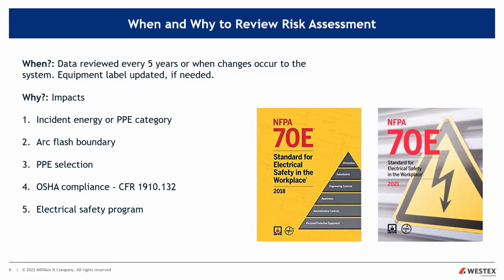Now, why? Well, of course, if things have changed, the incident energies change. Maybe the available fault current has gone up, or maybe you've changed the setting on a circuit breaker where it's a longer clearing time, and that can affect the incident energy. It could also affect if the PPE category is still valid. If you've changed the system a little bit, will it meet those parameters? Of course, if it's higher incident energy, maybe the arc flash boundary is longer than previous, or maybe shorter if you have new equipment. It may reduce your incident energy, especially on some of the newer equipment.